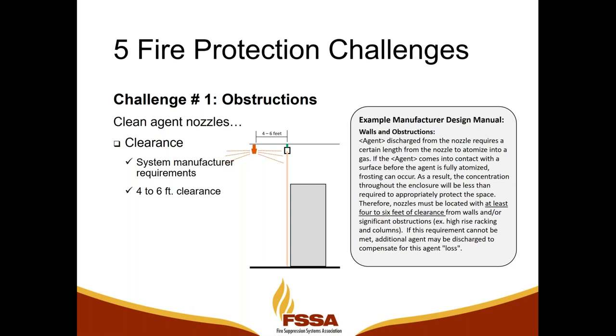If in an existing data center an aisle containment partition is installed next to a nozzle, it may be installed so close that the clearance requirement cannot be met. And so you run the risk of a phenomenon called frosting. Some people call it splashing, where that liquid agent coming out of the nozzle hits that surface and takes a longer time to convert to a gas. So that could impact the time to build an extinguishing concentration in that space.